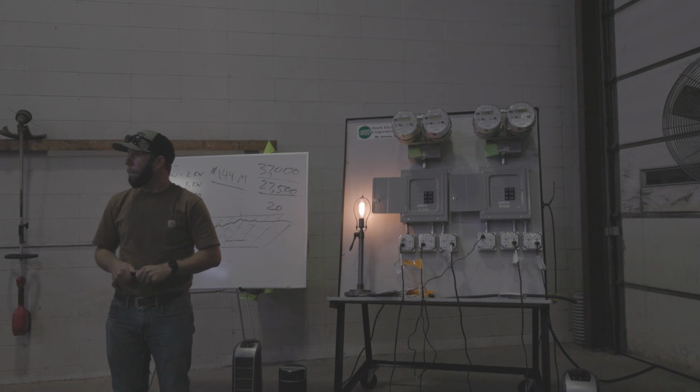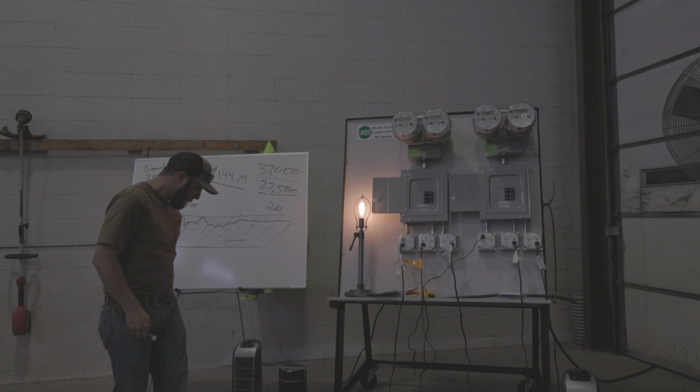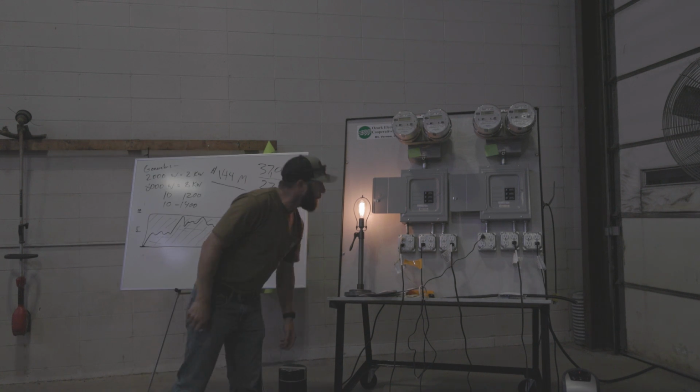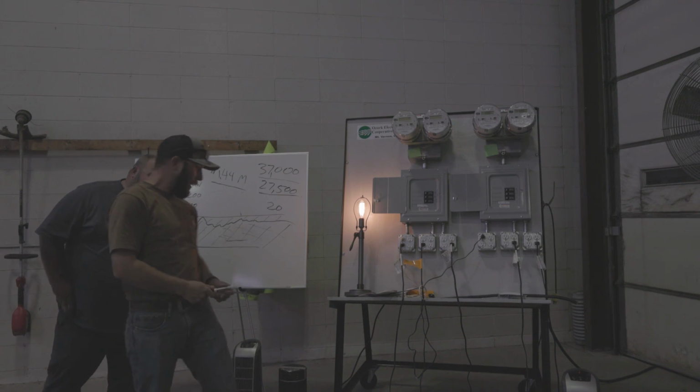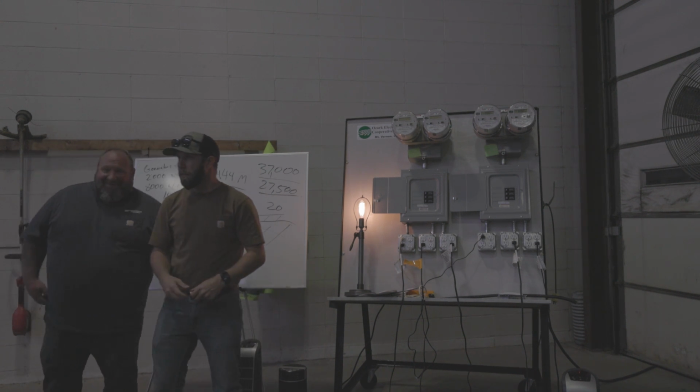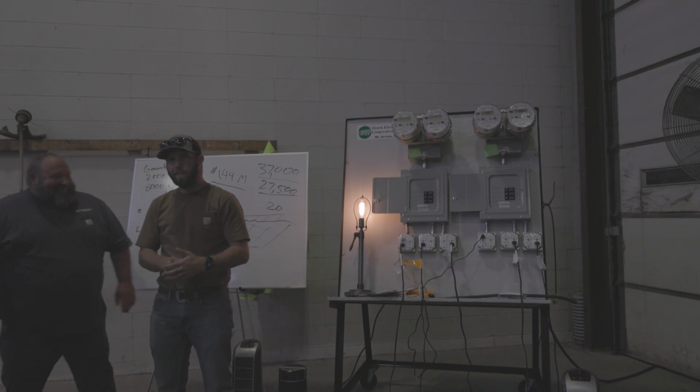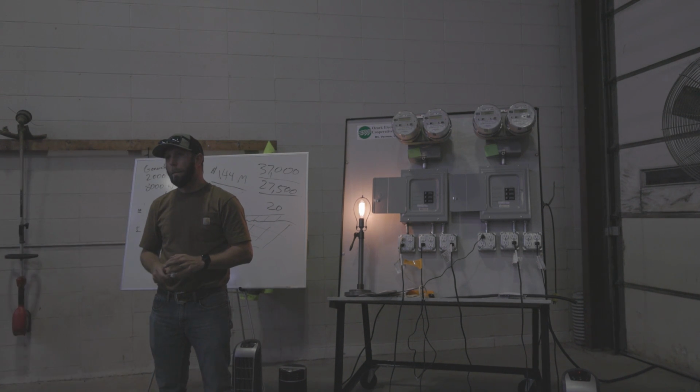The way the base demand is figured is we have 25 substations. Ozark Electric has 25 substations that we use our power on. Those substations are looked at every hour. They're on an hourly demand, and they are stored every hour of the billing period. Then for every substation, whatever their peak was for that month, they're all added together, and that is the base demand for that month.